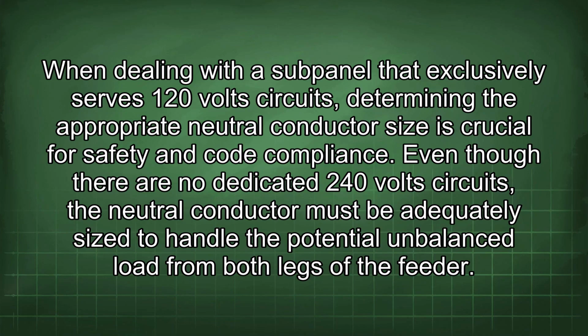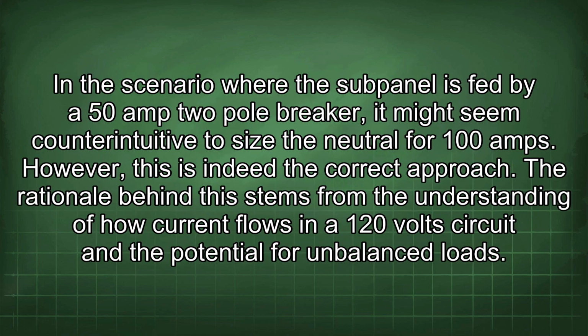When dealing with the subpanel that exclusively serves 120-volt circuits, determining the appropriate neutral conductor size is crucial for safety and code compliance. Even though there are no dedicated 240-volt circuits, the neutral conductor must be adequately sized to handle the potential unbalanced load from both legs of the feeder. In the scenario where the subpanel is fed by a 50-amp 2-pole breaker, it might seem counterintuitive to size the neutral for 100 amps. However, this is indeed the correct approach.